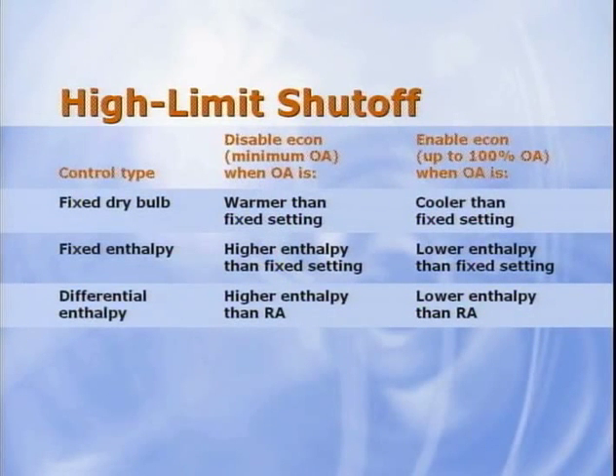Differential or comparative enthalpy control uses sensors to measure and calculate the enthalpy of both the outdoor and return air streams, and uses as much of the lower enthalpy air as it can to satisfy the cooling load. The economizer is disabled whenever the outdoor enthalpy is higher than the return air enthalpy. The installed cost of differential enthalpy control is higher than for the other control methods because it requires humidity sensing for both outdoor and return air. But in a VAV system, it typically results in the most cooling energy saved.